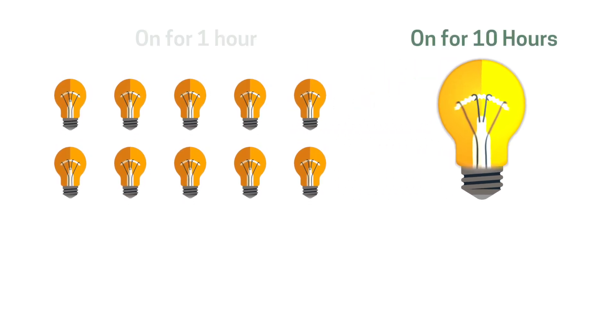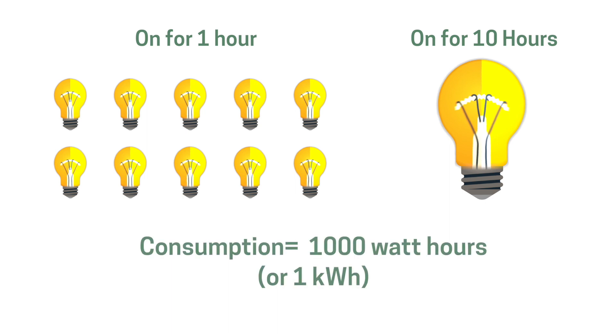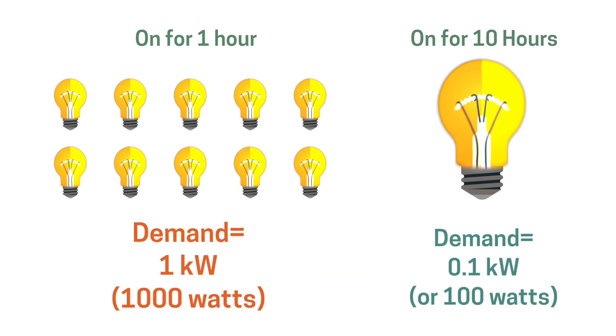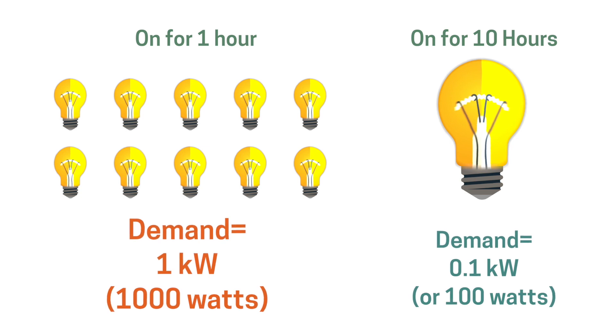Whether we have a single 100-watt light bulb running for 10 hours or a bank of 10 100-watt bulbs running for 1 hour, our consumption is the same—1 kilowatt hour or 1,000 watt hours. The bank of 10 100-watt light bulbs, however, demands 10 times more electricity from the utility than a single 100-watt bulb does. So even though the electrical consumption is the same in these two cases, the demand is much different. Simply put, the bank of 10 100-watt bulbs demands more energy from the utility.